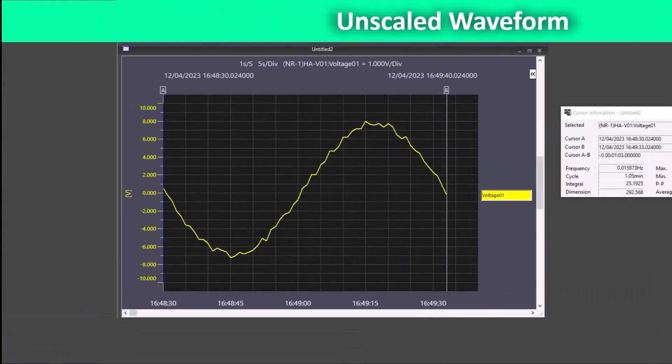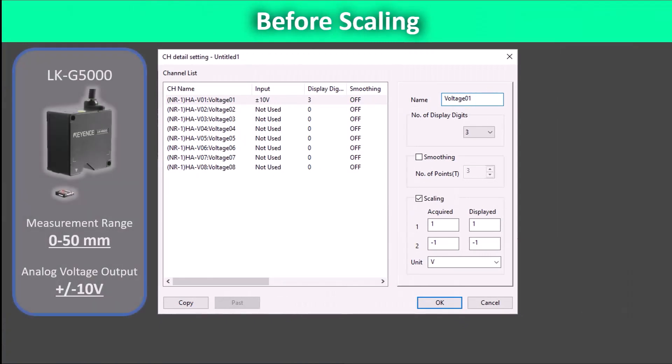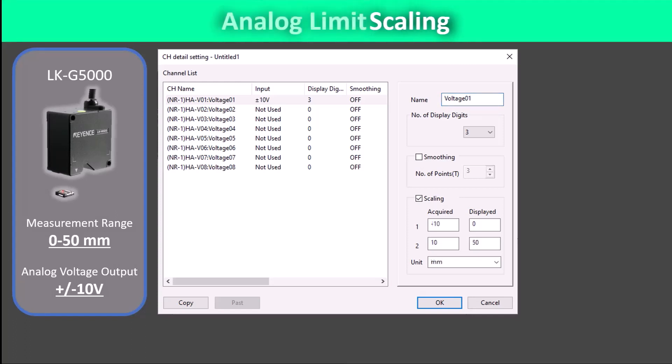To take a look at the process for analog limit scaling, let's take our unscaled waveform and use an example Keyence sensor, the LKG. This laser sensor can be set to have a measurement range from 0 to 50 millimeters with an analog voltage output of plus and minus 10 volts. We are going to use these values to set scaling point 1 to be negative 10 volts equals 0 millimeters. Scaling point 2 will be positive 10 volts to equal 50 millimeters.